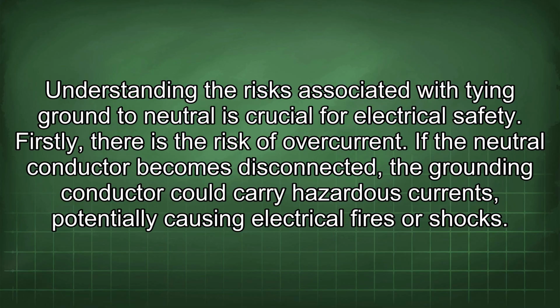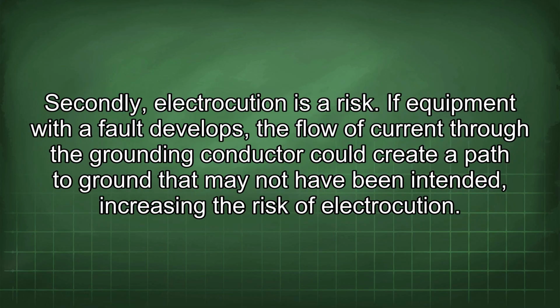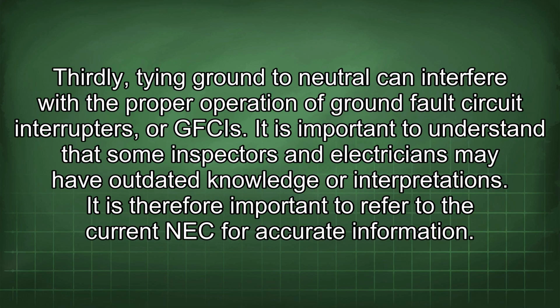Firstly, there is the risk of overcurrent. If the neutral conductor becomes disconnected, the grounding conductor could carry hazardous currents, potentially causing electrical fires or shocks. Secondly, electrocution is a risk. If equipment with a fault develops, the flow of current through the grounding conductor could create a path to ground that may not have been intended, increasing the risk of electrocution. Thirdly, tying ground to neutral can interfere with the proper operation of ground fault circuit interrupters, or GFCIs.